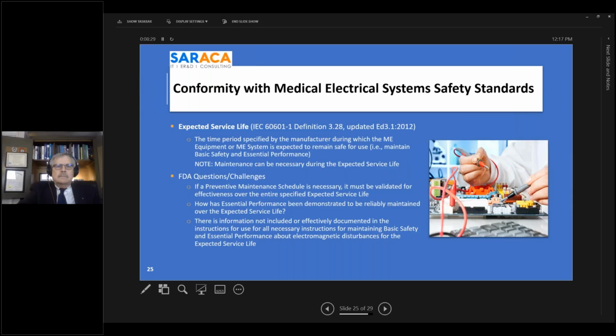These folks, and all folks, are expected to make sure they understand that through the application of risk management, their design architecture, and their verification of effectiveness, that it lasts that long. Now you're talking reliability studies that folks hadn't planned for before or hadn't fully conducted for essential performance and basic safety over that time frame. A case in point: a PM was performed on an infusion pump that actually caused a failure of essential performance. It resulted in a Class 1 recall in 2020, and it caused the insulin pump to shut down. So their maintenance wasn't effective, their instructions weren't effective, and the way to control that was ineffective.